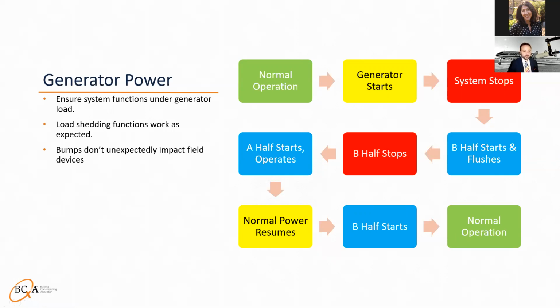Other things that you'll see in generator power bumps is that devices will break. VFDs will burn out or photo eyes will just pop. They won't work anymore. So you'll want to make sure that those things are handled correctly and that they're annunciated correctly on the system.